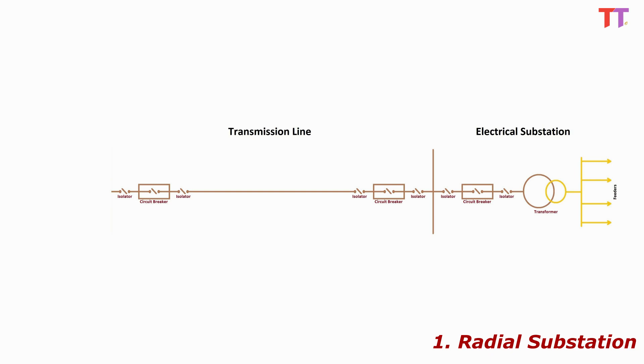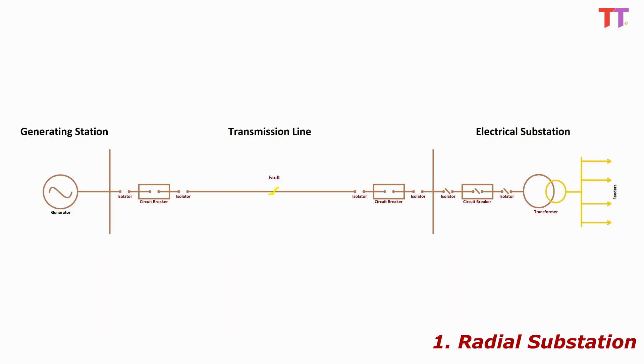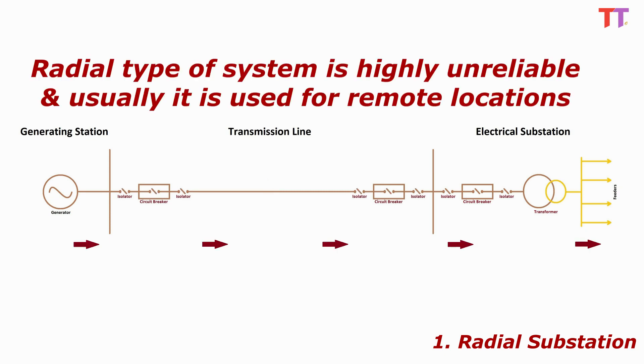However, in the event of source failure or in case of fault on the source line, the complete substation goes dark, subsequently causing complete power breakdown of the connected load. Hence such a system is highly unreliable and usually used for remote locations.